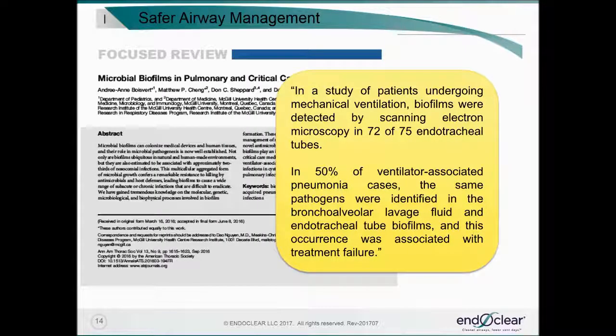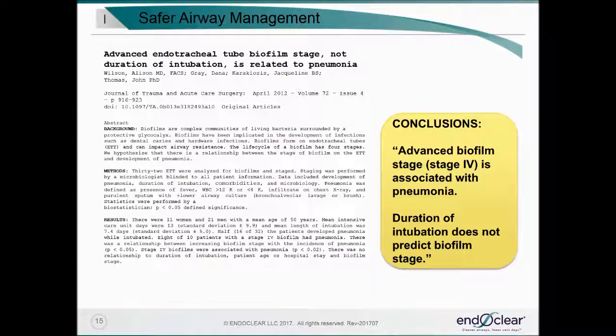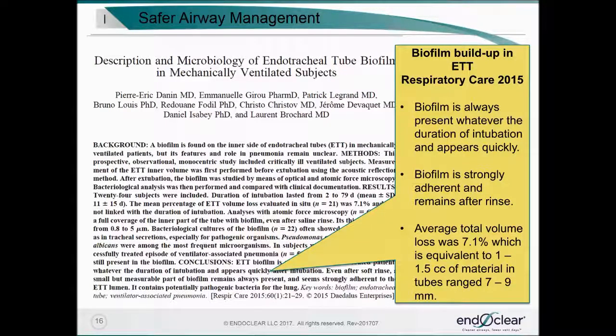As important as endotracheal tube narrowing can be, that is not the only issue with current standard of care treatment. We now know that nearly all endotracheal tubes develop biofilm, which has been implicated in the pathophysiology of ventilator-associated pneumonia. We also know that biofilm matures through 4 stages, with stage 4 being associated with pneumonia in the ventilated patient. This maturation may occur quite quickly. This article in Respiratory Care investigated both the obstruction and the biofilm components of artificial airway deterioration. They found that biofilm is always present in endotracheal tubes, it's quite adherent to the inner lumen of the tube, and that the average total volume loss was about 7%, which corresponds to between 1 and 1.5 cc's of retained secretions.